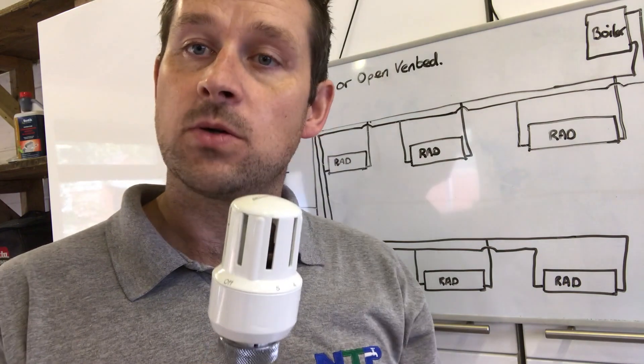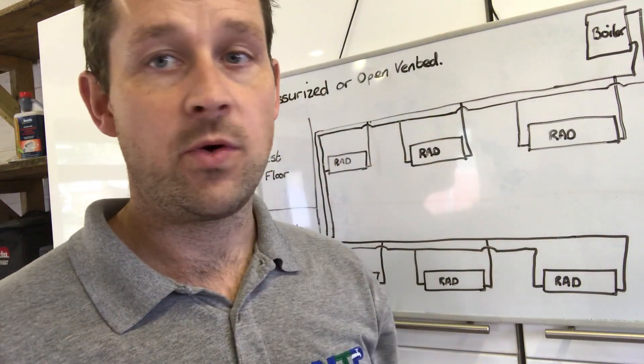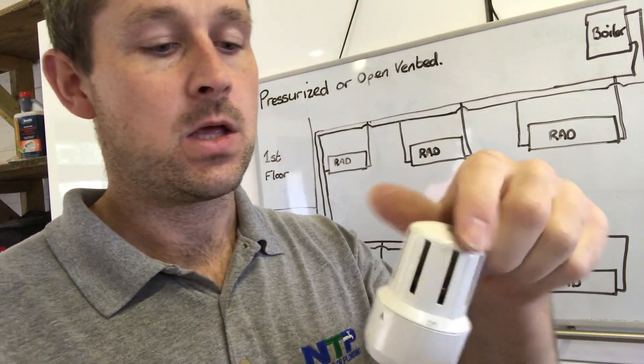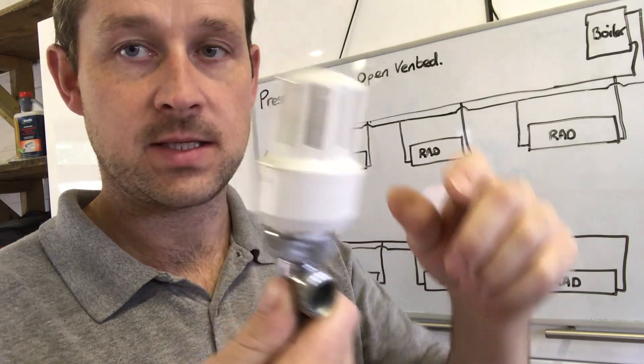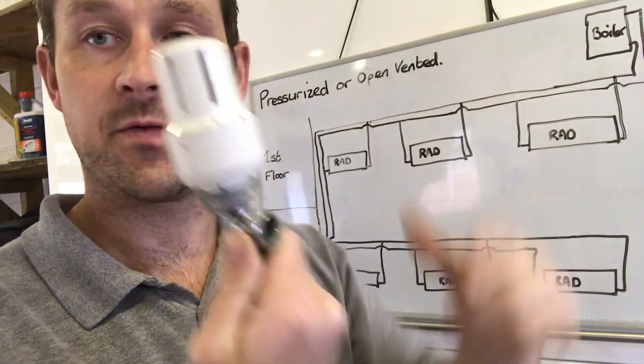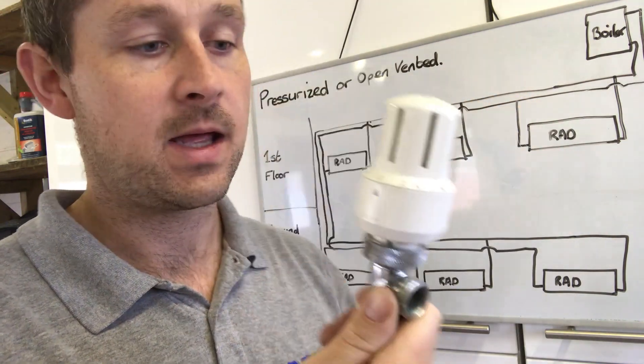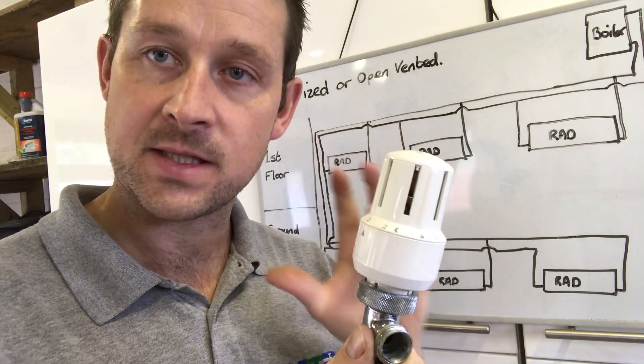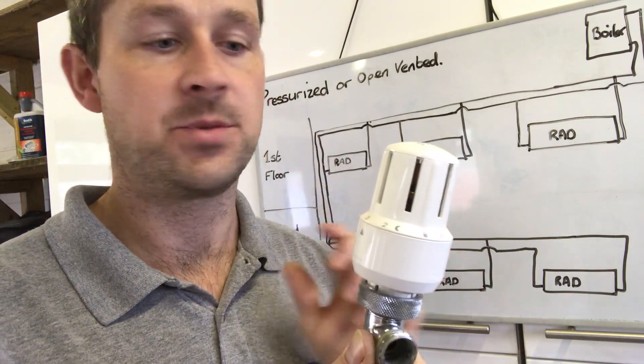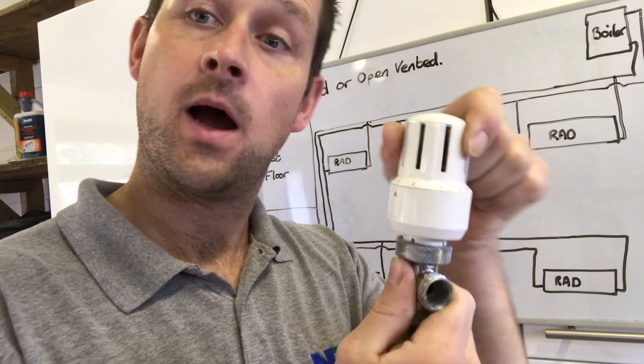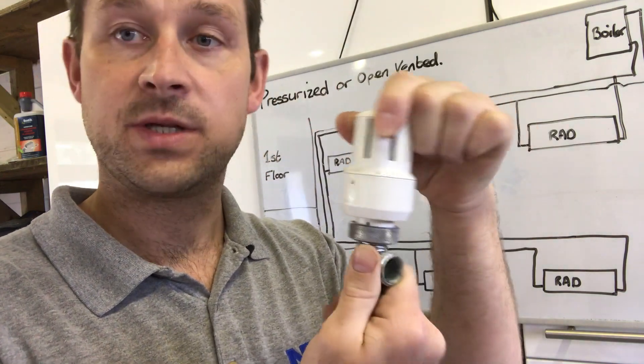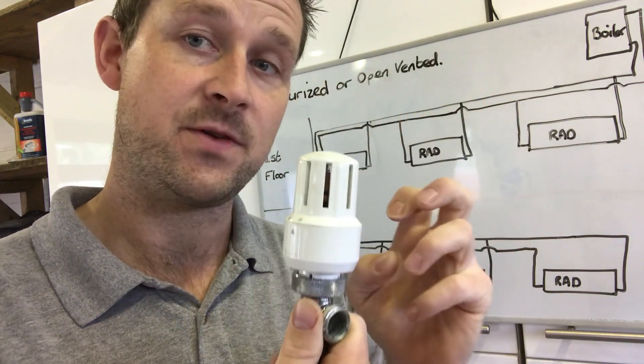When you do a new install, when you install a new central heating system or even just one radiator, you want to have this set to three, so halfway in between. So when you balance the system, the customer has the option of increasing slightly or reducing the heat if they want to for that individual radiator.